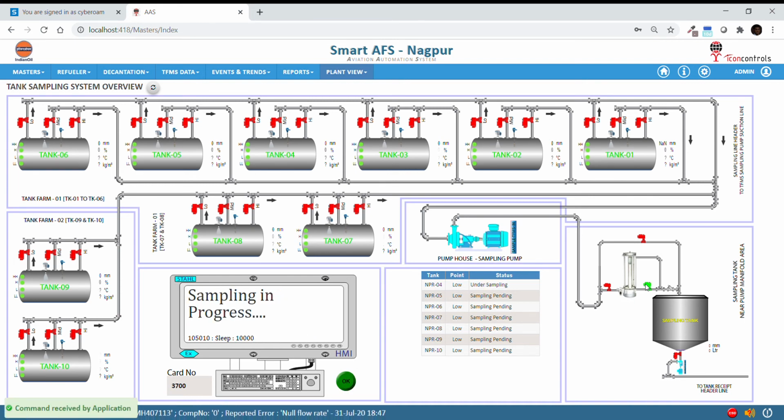That is the emptying of the glass jar contents through the outlet glass jar SOV, and then the bypass of the existing contents in the pipeline. That is, the pump is running, the point valve is active, the bypass valve is active. Once the flushing is done, then we will see that the SOV and the inlet glass jar will open, which will fill up the new product in the line into the glass jar.